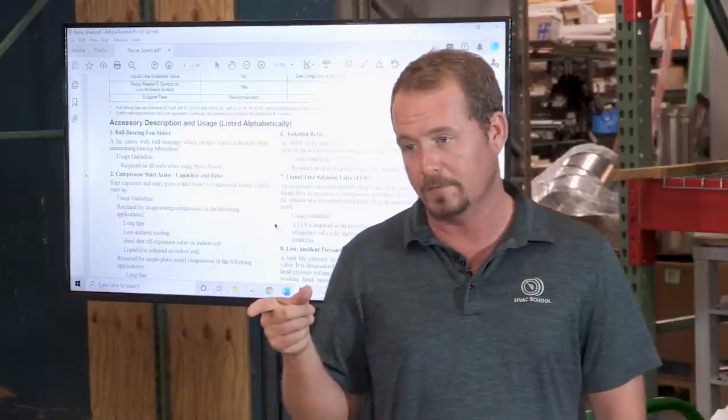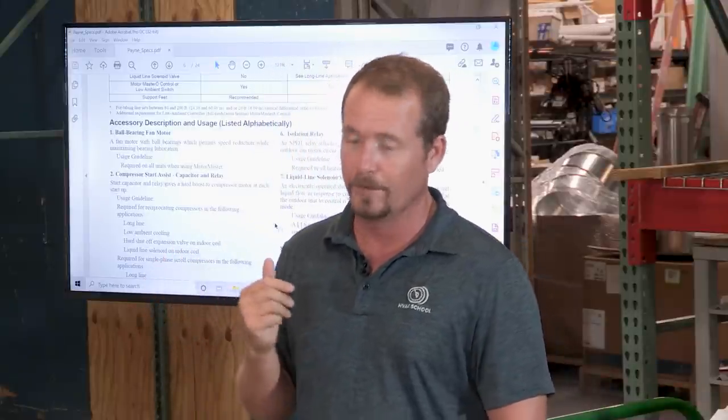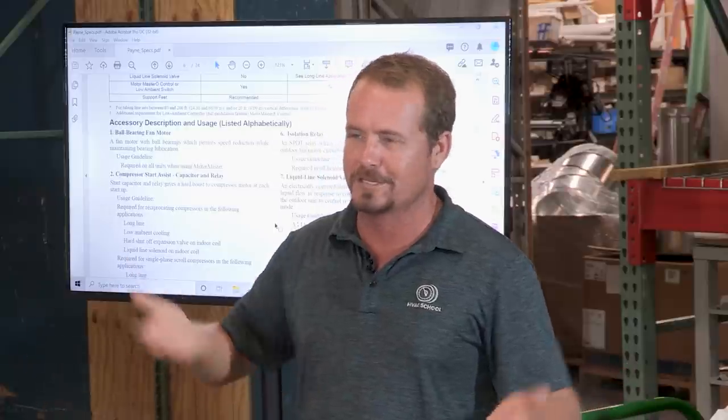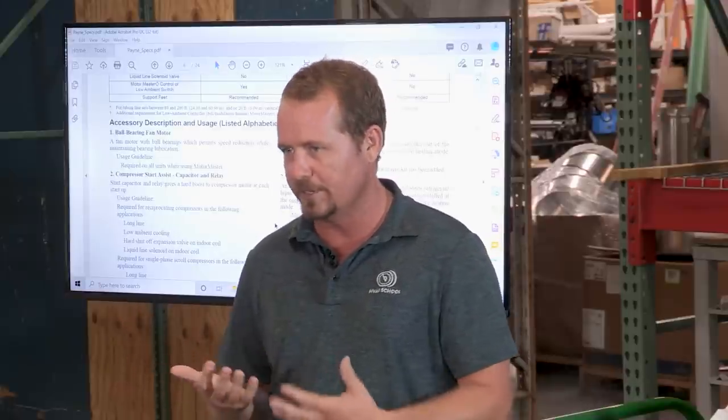What's the problem with it, Bert, with that design? I would say the strain it puts on your compressor at that low pressure. That is actually one side of it, and that's why you wouldn't want to set your low pressure control very low at all. You don't need to pump it down to a really low level. You're not trying to open the valves, right? So if you're working on a 410A system, you would just set it, maybe, I don't know, 80 PSI, something like that. I'm just making that up, but you wouldn't need to set it that low at all. So yes, it is a little additional energy, but only a little bit if you do it right.